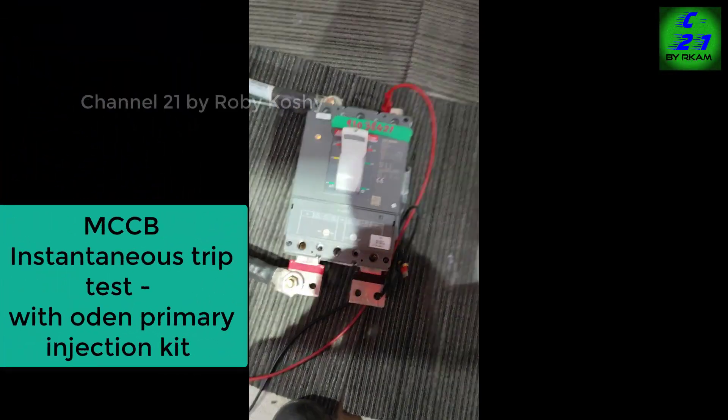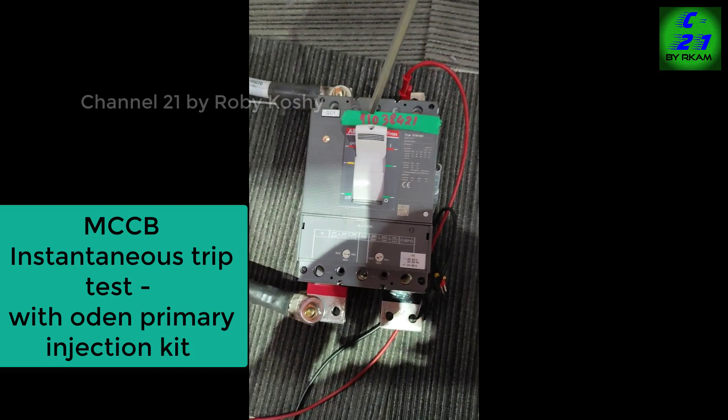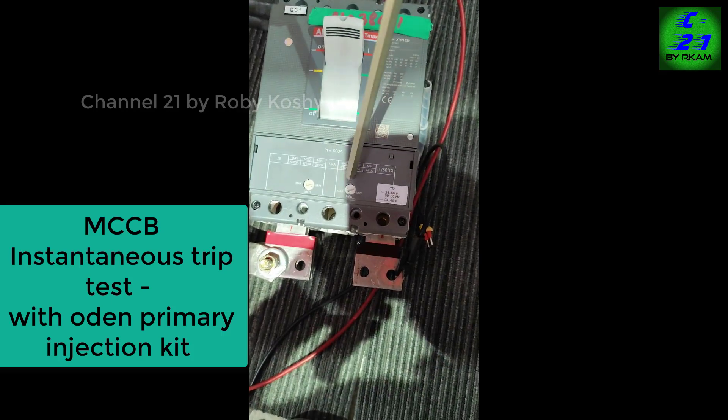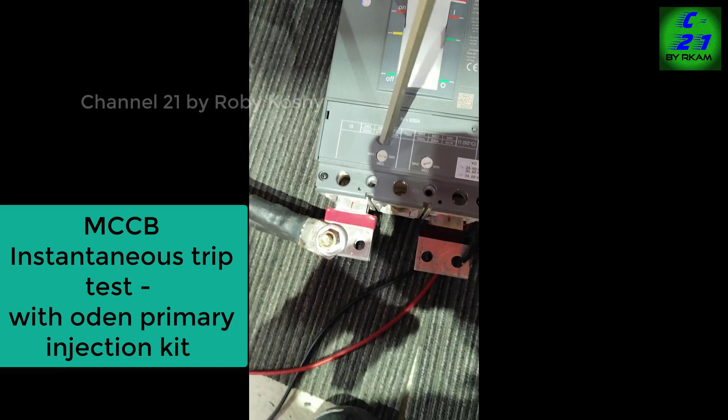As per your request, again we are testing the same 630A breaker. This came from Saudi Arabia — the serial number you can see here. The breaker is set with the overload at maximum and instantaneous at minimum.